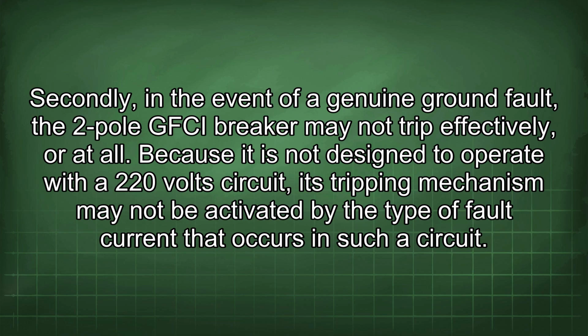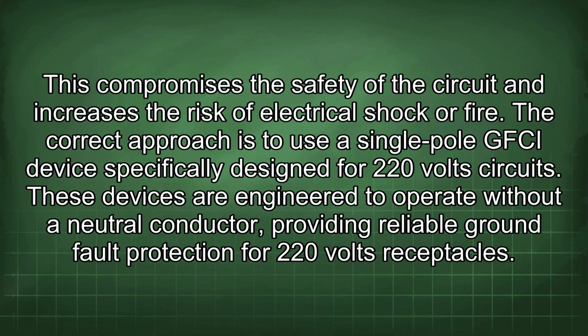Secondly, in the event of a genuine ground fault, the 2-pole GFCI breaker may not trip effectively or at all. Because it is not designed to operate with a 220-volt circuit, its tripping mechanism may not be activated by the type of fault current that occurs in such a circuit. This compromises the safety of the circuit and increases the risk of electrical shock or fire.